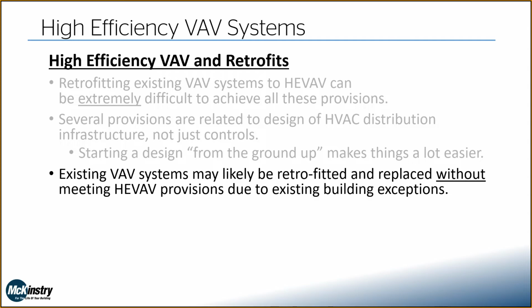But that said, existing VAV systems can very likely be retrofitted and replaced without meeting all of these provisions due to existing building exceptions. So there is code language on existing buildings that says we won't make you tear out something that is already installed and met code at the time of installation. So that would include all of the ductwork out in the system.